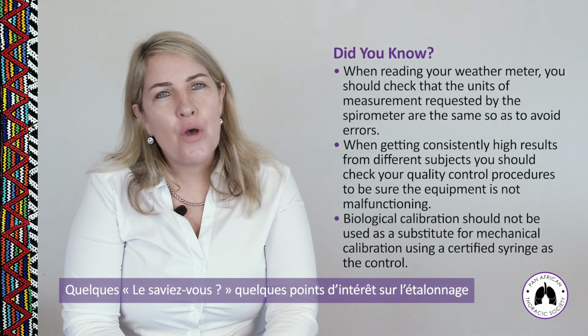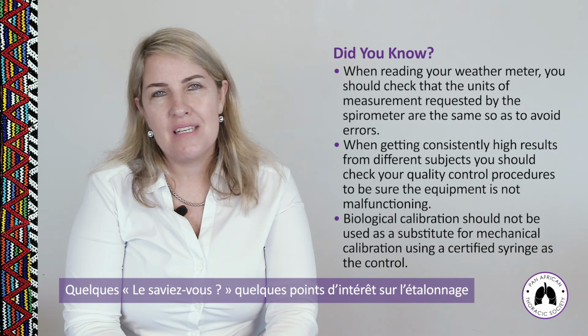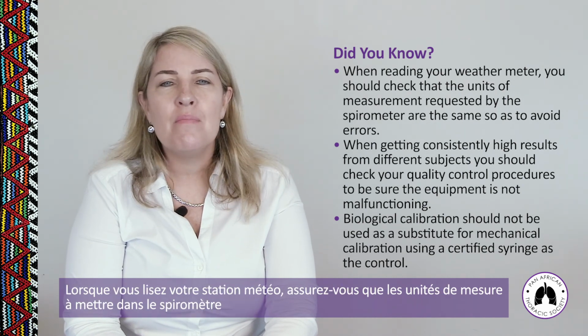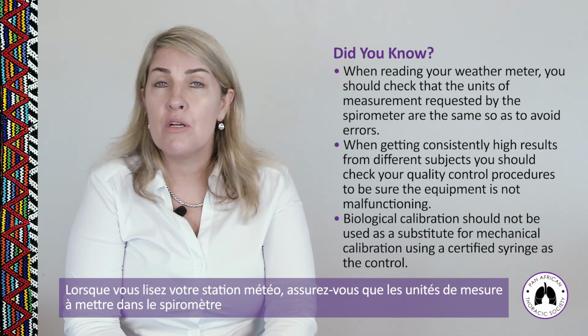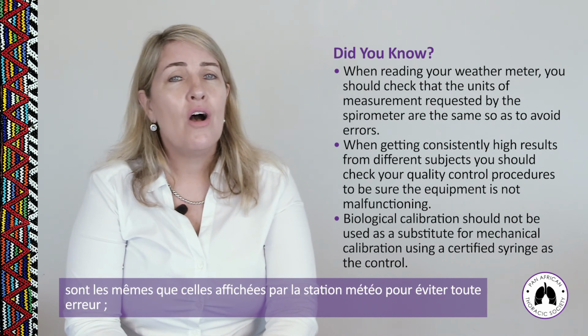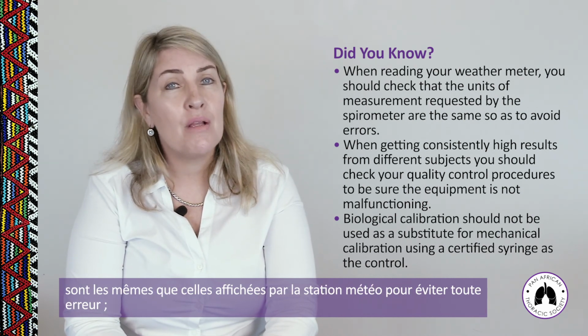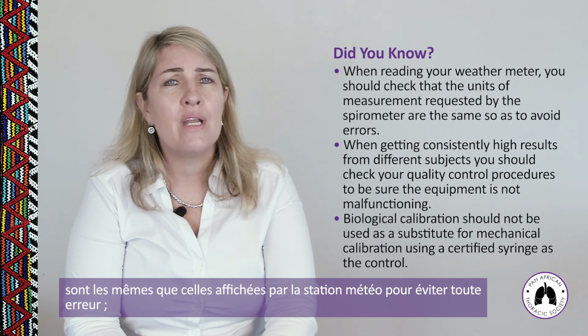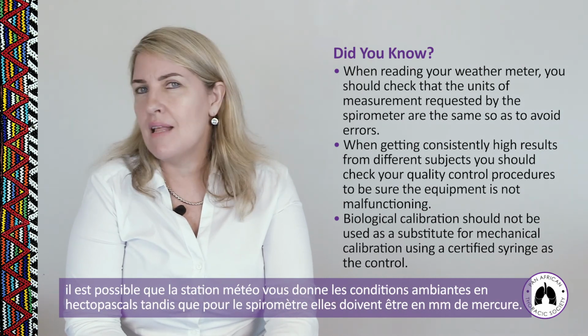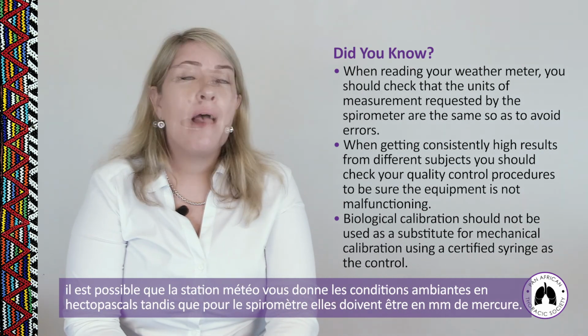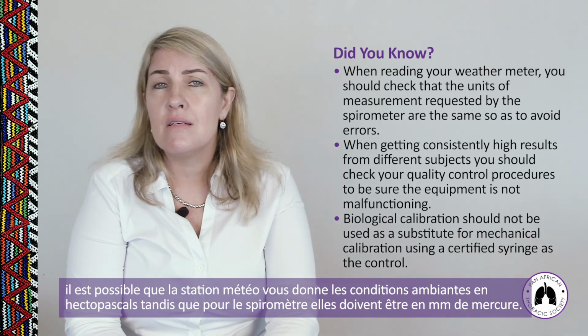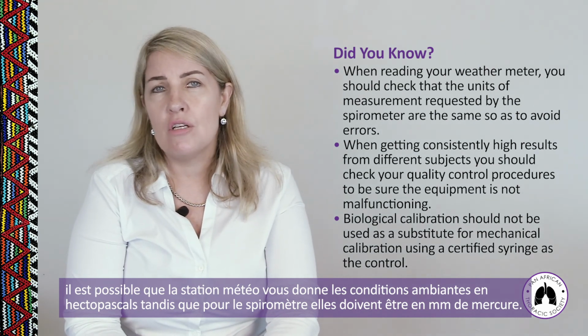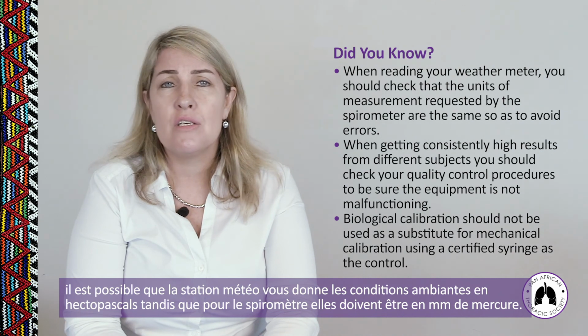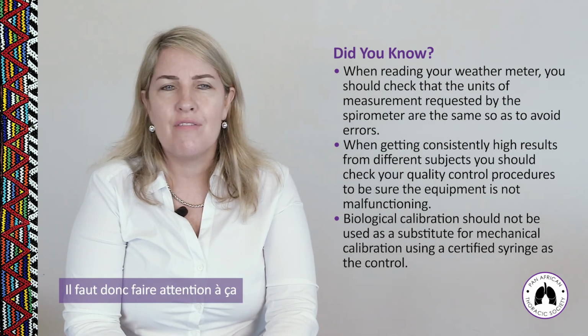A few little did you knows, some interesting facts about calibration. When reading your weather meter, you should check that the units of measurement requested by the spirometer are the same as being read from the weather meter, so as to avoid errors. What can happen is that the weather meter may give you the ambient conditions in hectopascals, but the spirometer might ask for the answers in millimeters of mercury. So be careful to check for that.